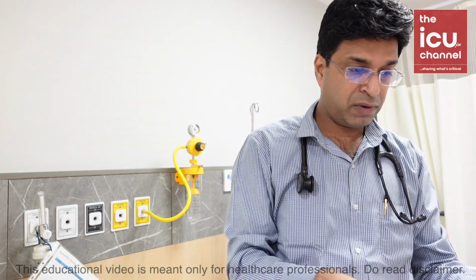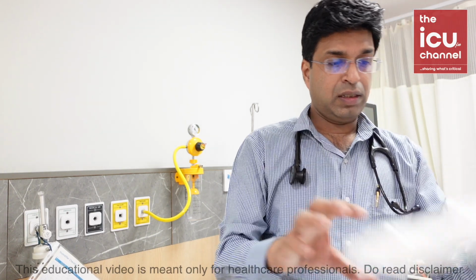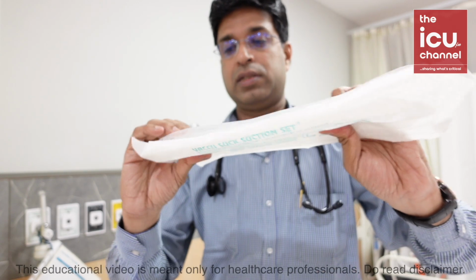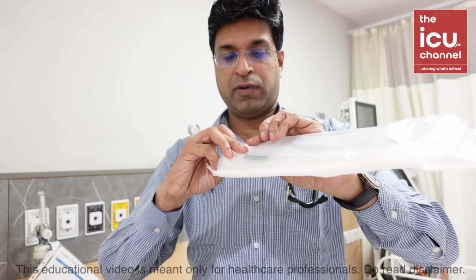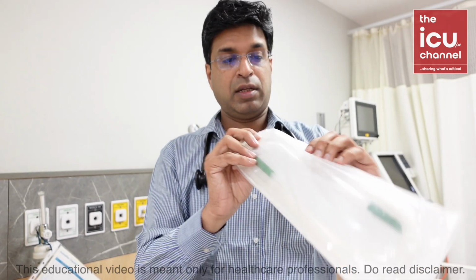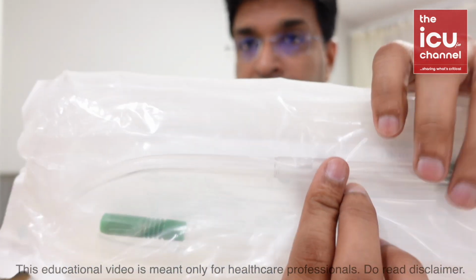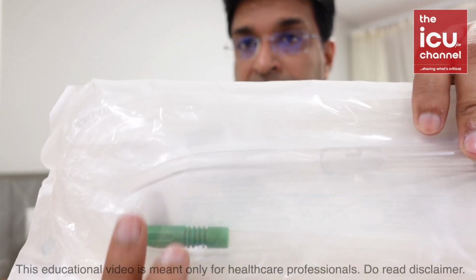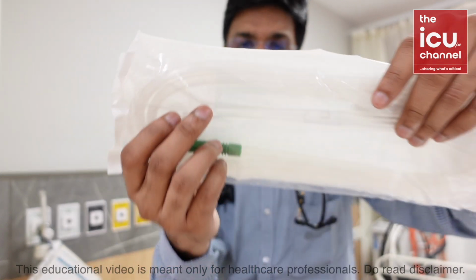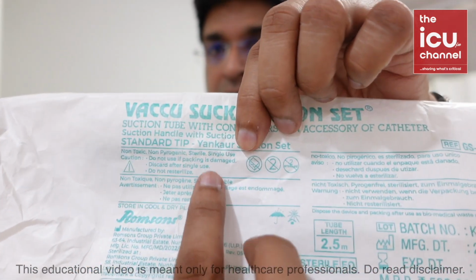There is one more cannula, a bigger, tighter one called the Yankauer cannula. This suction catheter is bigger, it gets connected into the vacuum port, and it's called Yankauer suction. You can see here. Yankauer is very useful where secretions are too large in number or too thick to be removed with the soft cannula. So these are vacuum suction ports, very important ones.